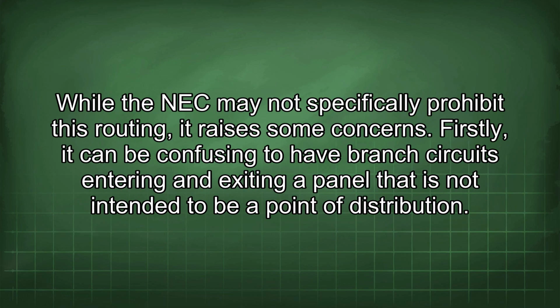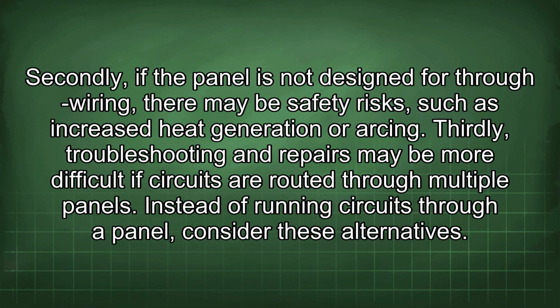While the NEC may not specifically prohibit this routing, it raises some concerns. Firstly, it can be confusing to have branch circuits entering and exiting a panel that is not intended to be a point of distribution. Secondly, if the panel is not designed for through wiring, there may be safety risks such as increased heat generation or arcing. Thirdly, troubleshooting and repairs may be more difficult if circuits are routed through multiple panels.